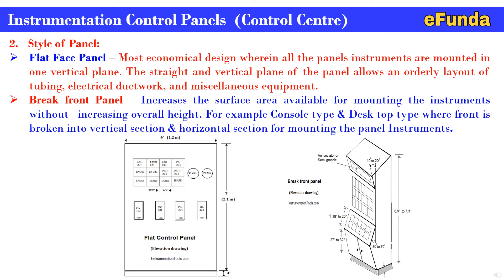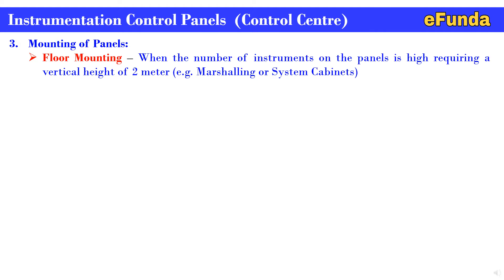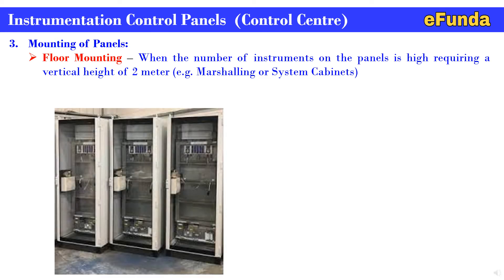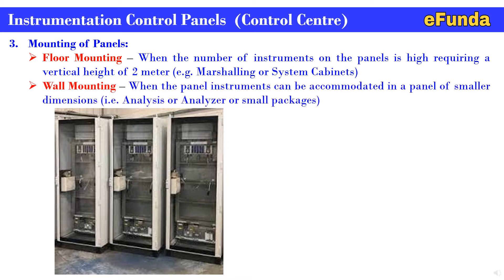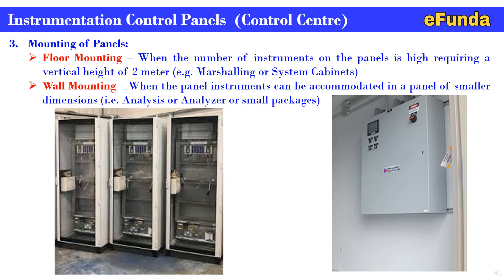Mounting of panel: first, floor mounting — when the number of instruments on the panel is high, requiring a vertical height of 2 meters, for example marshaling or system cabinets. You can see the photograph where a 2-meter height vertical panel is floor-mounted to cover the required number of instruments needing high space. Second, wall mounting — when the panel instruments can be accommodated in a panel of smaller dimensions, such as analyzers or small packages. The photograph shows wall-mounted panels for small or fewer instruments requiring less space.